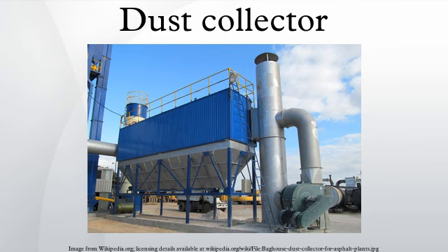The following points should be considered when selecting a unit collector. Cleaning efficiency must comply with all applicable regulations. The unit maintains its rated capacity while accumulating large amounts of dust between cleanings. Simple cleaning operations do not increase the surrounding dust concentration. It has the ability to operate unattended for extended periods of time. Automatic discharge or sufficient dust storage space to hold at least 1 week's accumulation. If renewable filters are used, they should not have to be replaced more than once a month.